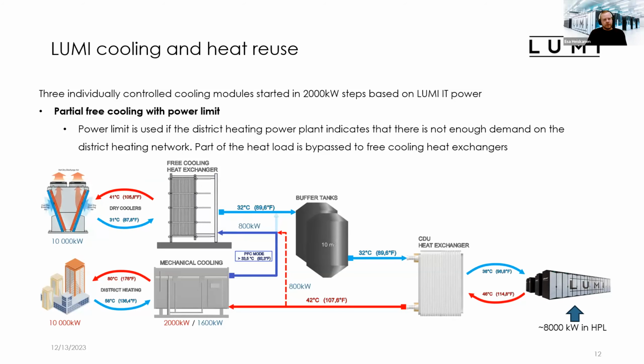Then we have this partial free cooling with power limit, and this power limit is used if the district heating power plant indicates that there is not enough demand on the district heating network. Then we bypass part of the heat load from the Lumi to the free cooling heat exchangers, so we can adjust the heat production based on the demand that there is on the district heating. And this usually only applies in situations where the daytime demand is lower than the nighttime, and we have pretty much just started the district heating production season, or it's closing to the end.